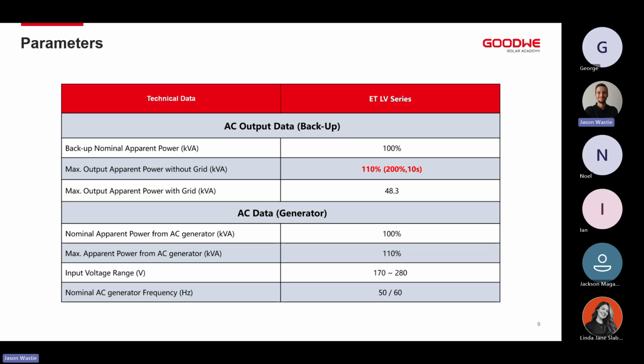If there's enough PV available, it will supply as much of the load as possible. If there's battery available, we supply towards the loads, but it will never pull more than the BMS allows on the inverter, on the battery, and will never use more than we have to from both of those. If there is any big startup or big load that starts up for a short amount of time, up to 10 seconds, we can handle that for double the amount of PV inverter capacity.